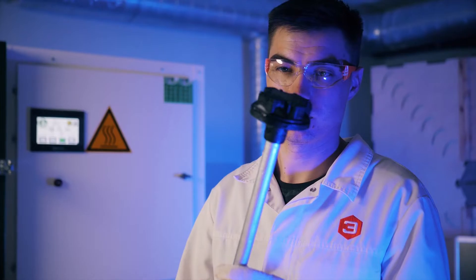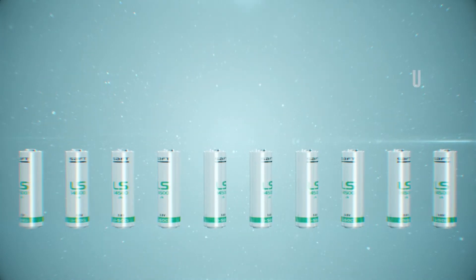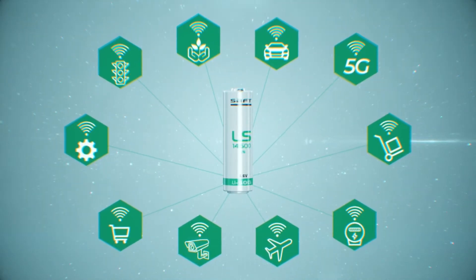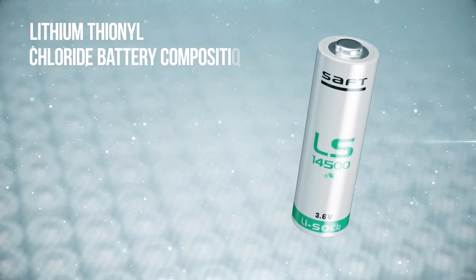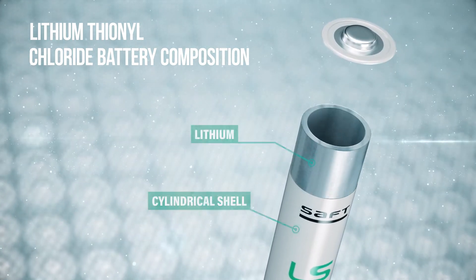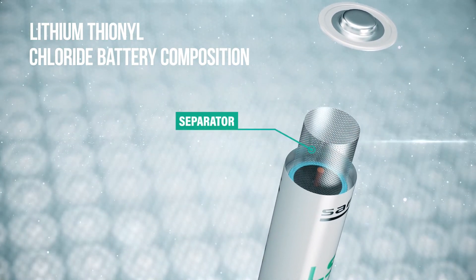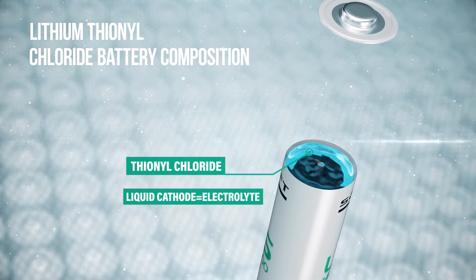We often hear that the TDB-LE sensor itself and its battery will not work in northern regions. Before choosing a battery, we conducted experiments and testing with various manufacturers and settled on SAFT, because during testing it proved better than others at low temperatures due to its use of lithium-thionyl chloride chemistry. Discharge and capacity reduction at negative temperatures is the smallest of any manufacturer on the market. We have a direct contract with the battery manufacturers, which allows us to confirm their authenticity.